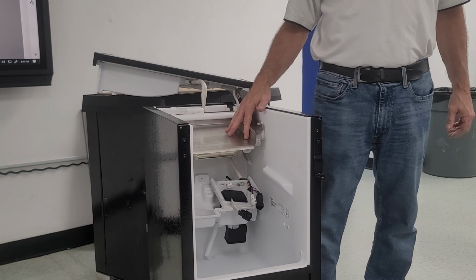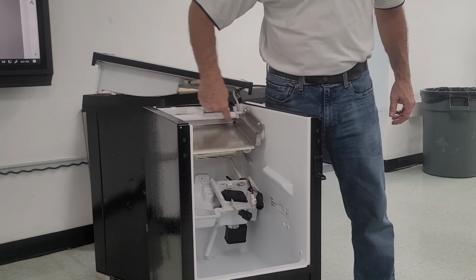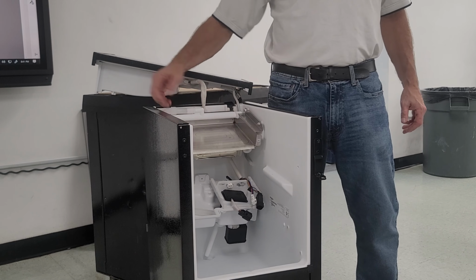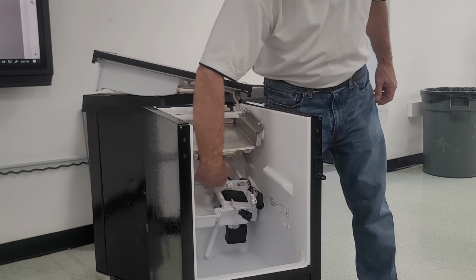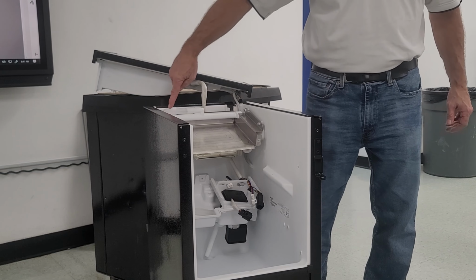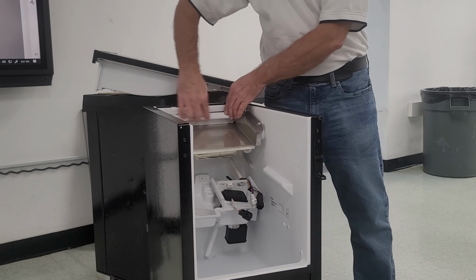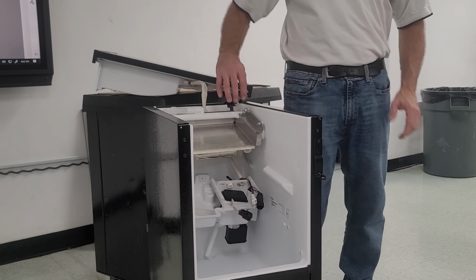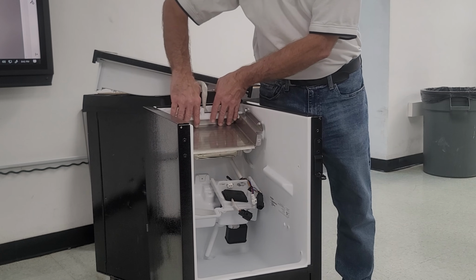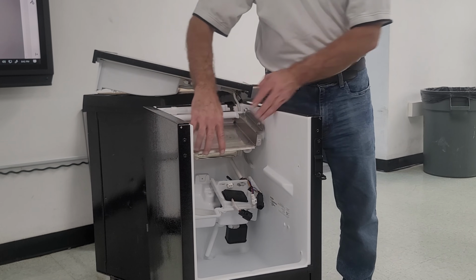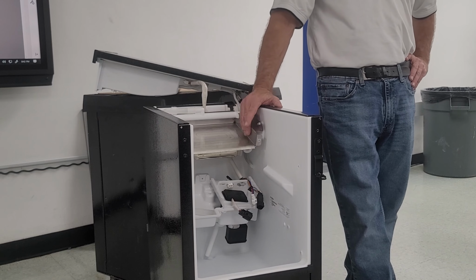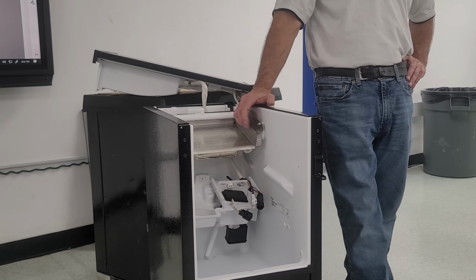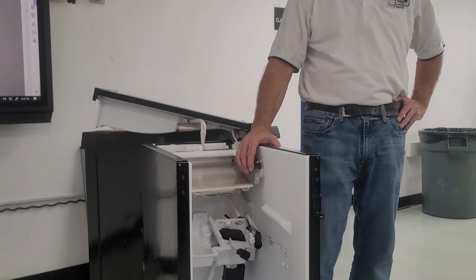You can see it a little bit more clearly now. This right here is like a spreader, so that the pump pumps from down here, runs up through the back here, and runs through here, and then this spreads it out to a couple little holes like a sprinkler system, and then the water hits the evaporator and runs down. The biggest thing I see wrong with these, besides the water valve or the circulation pump failing, is, can you see these lines here?